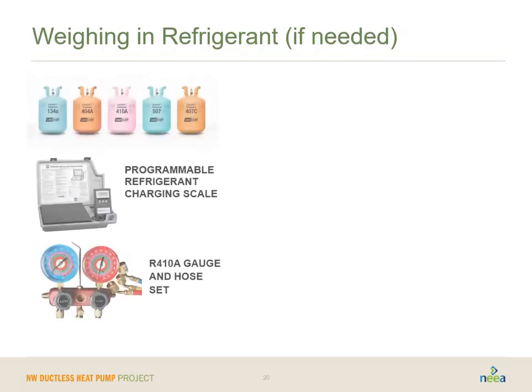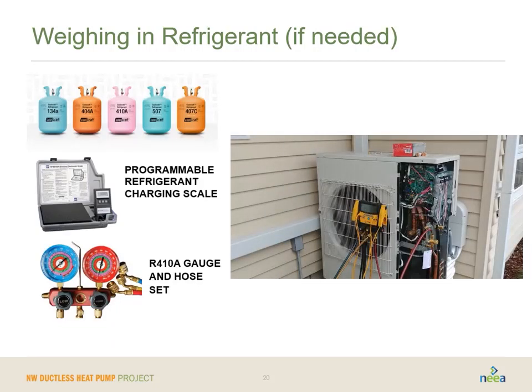Weighing in refrigerant. So I talked a little bit about this. You will need to have an EPA 608 refrigerant license in order to be able to handle refrigerant. And the EPA a couple of years ago passed new rules that have to do with handling and recording refrigerant that's weighed in and waste refrigerant after any job. So you're going to need to have that certification. You're going to want to have your programmable scale and your gauge and hose set in order to do this. Again, as I stated, for a lot of devices, if you're able to put them within 25 feet of line set run, you may not have to weigh in any refrigerant. But what we find is most contractors, while that's their first goal, will inevitably find some scenarios where they really do need to run it longer. So it is a good idea to get that refrigerant handling license and to make sure you have the right equipment to do this work.